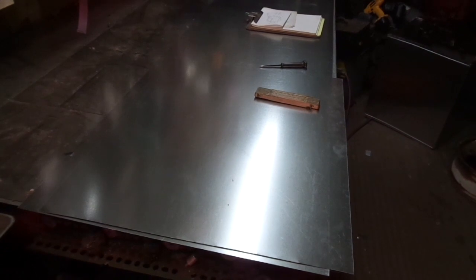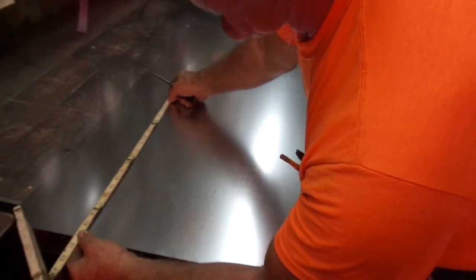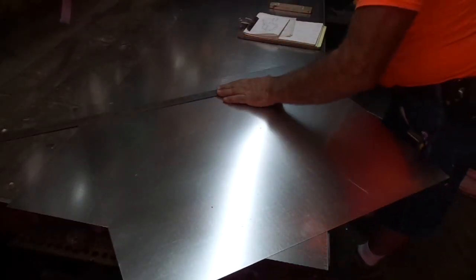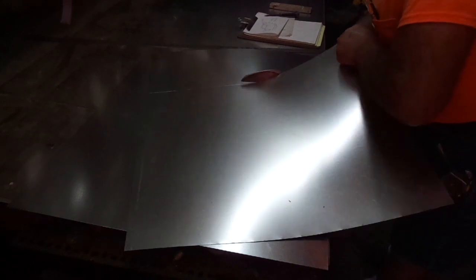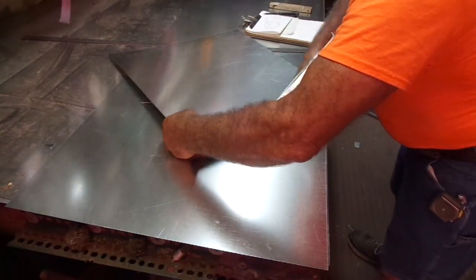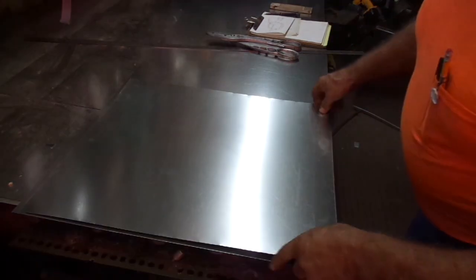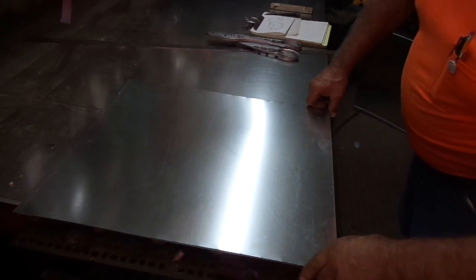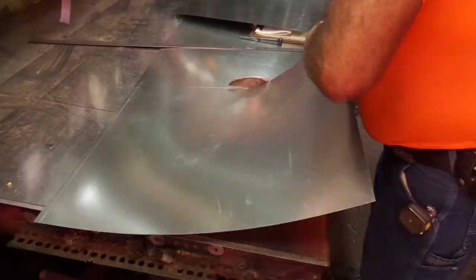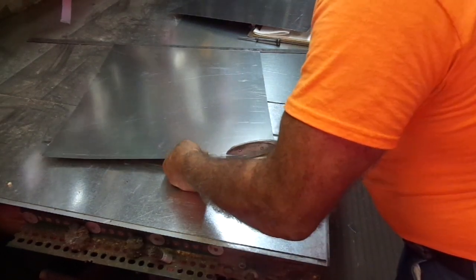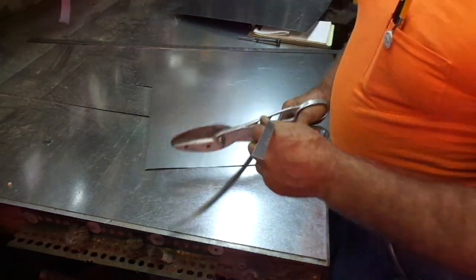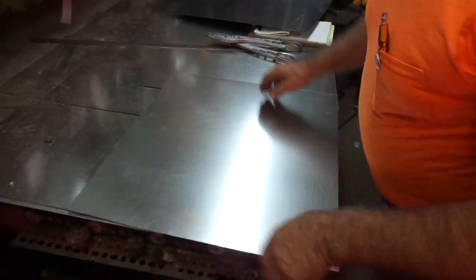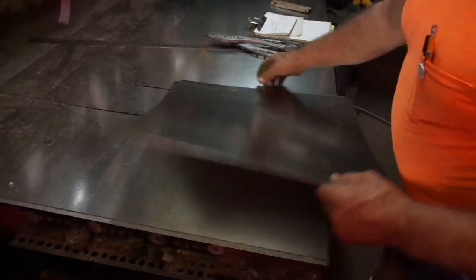But by the time we put the ends in it and tie those in, it's going to be just nice and rigid, support that furnace just perfectly. The one that's in there that we're removing right now is 28 gauge and it's been in there for 25 years. So this should do just fine. Now for the size, we want two, 20 and a quarter by 23 and a half. We get one left out of this sheet right here. So if I just come in 20 and one quarter inches, get our second mark, 20 and a quarter inches by 23 and a half. That's going to be my cut size. It's advisable to wear gloves and stuff. I've just never grown accustomed to them. Really cold weather, I'll wear gloves a little bit. But for the most part, your hands get a little tougher.